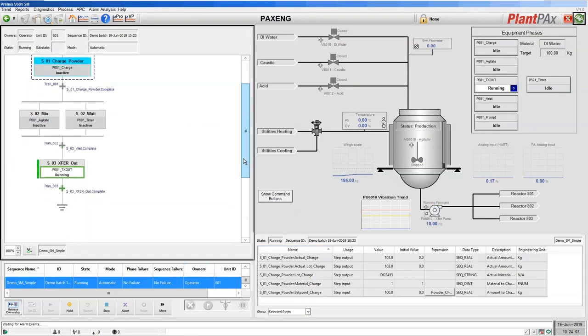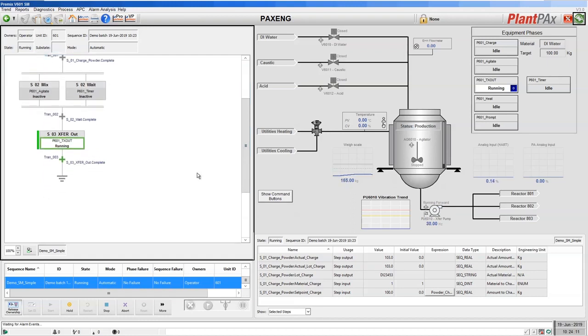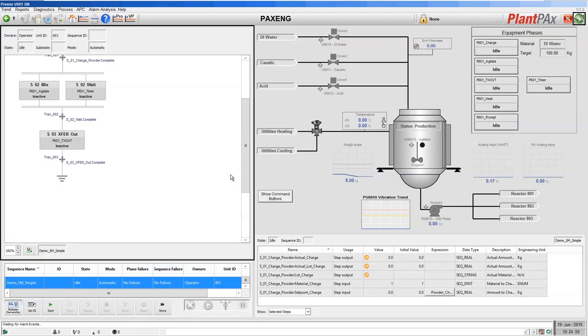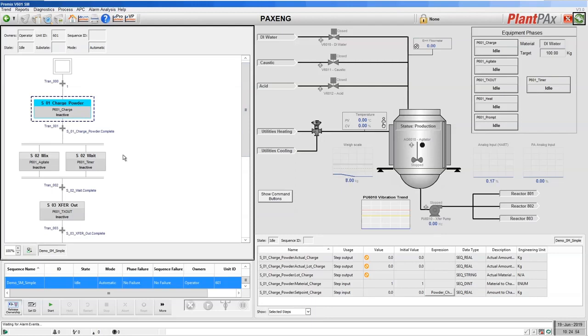Our sequence has moved on and we're agitating, and then finally it's moved on to the transfer out — the transfer phase is running and we're emptying our tank to final storage. Our sequence is now complete. We can reset that sequence back to idle and then run it again. With these ActiveX controls you have full control over execution: you can hold the sequence, restart it, stop it, abort it, take manual control of steps, manually start and stop them, or go back to a previous step to recover.